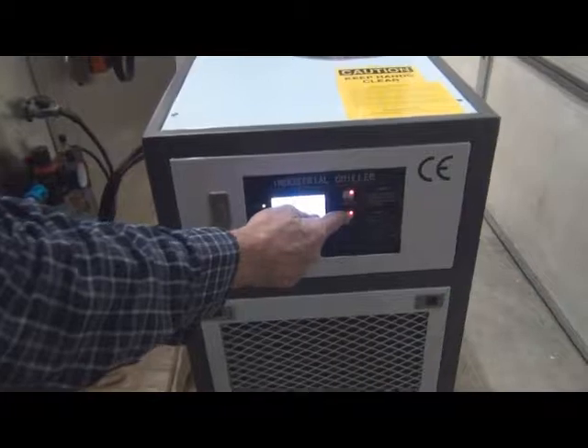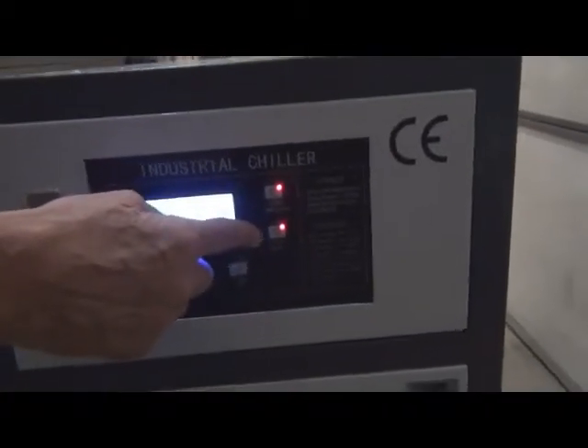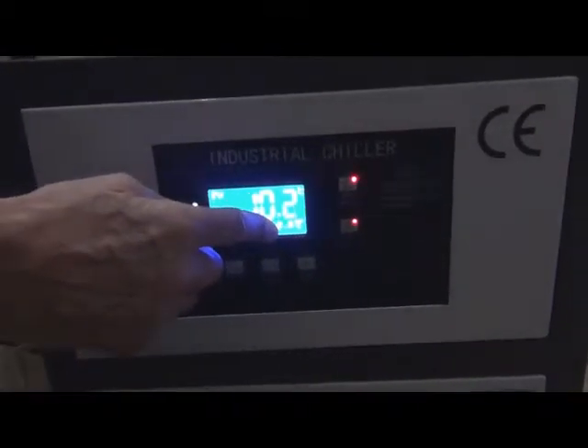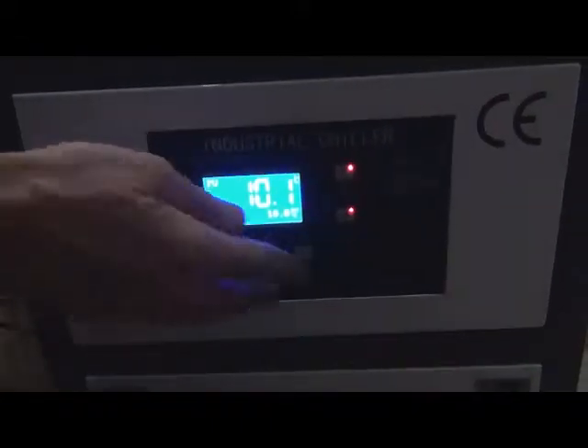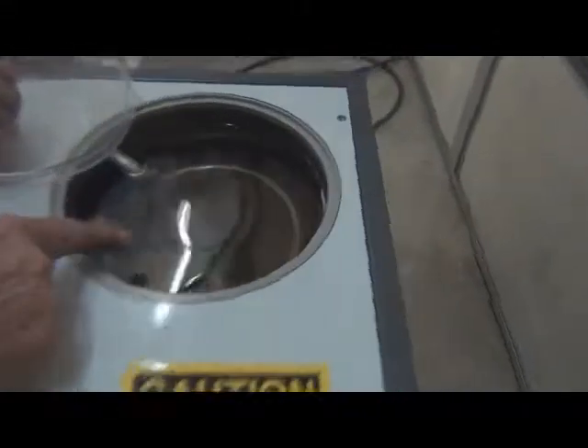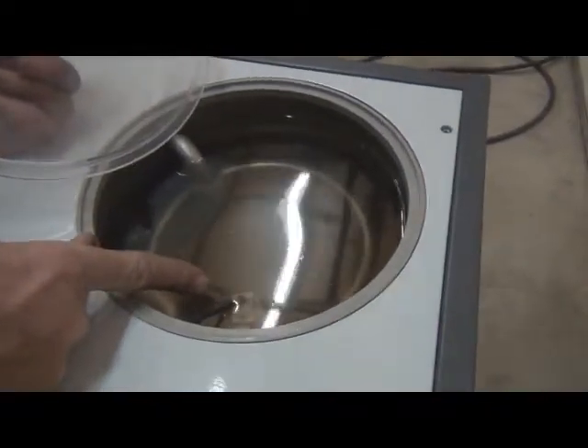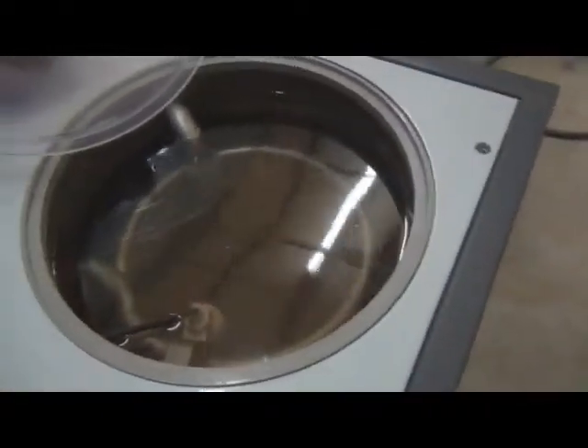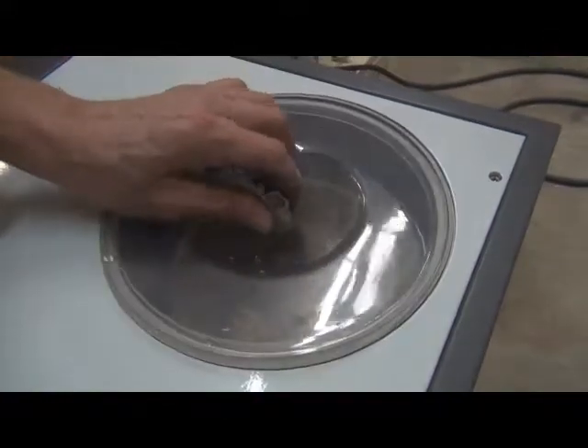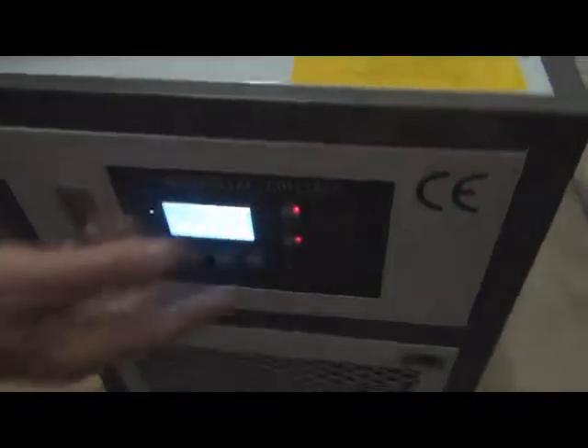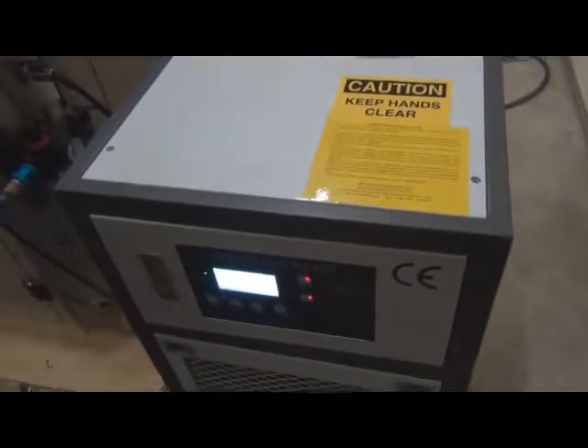That's right here, off and on. You want the setting to be 10 degrees C, which it is — already set, so you just turn it on. Now you fill the water here. Here's a water tank; just fill it up so it's above this float. If you go below that, you'll see this alarm light. To get rid of the alarm, just turn it off, fill it, turn it back on, and the alarm will reset itself.